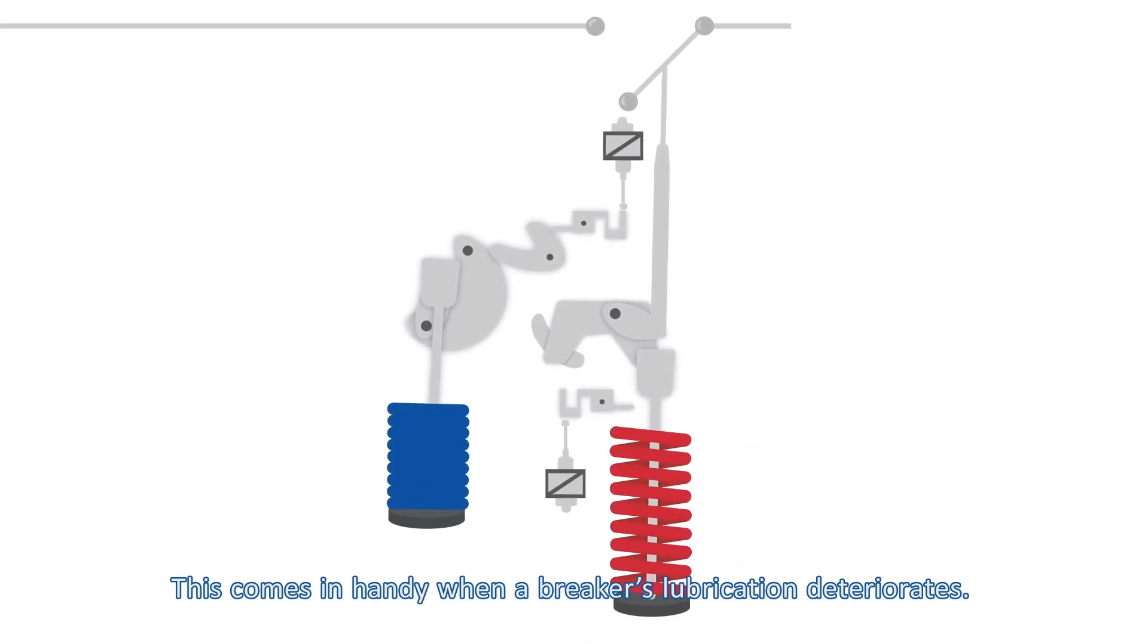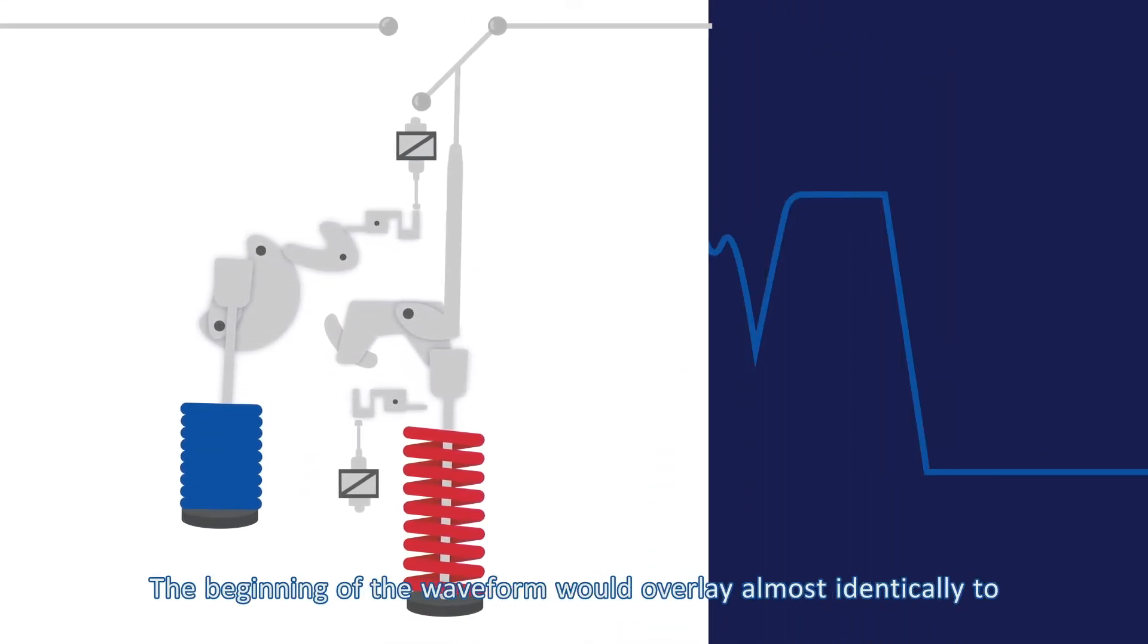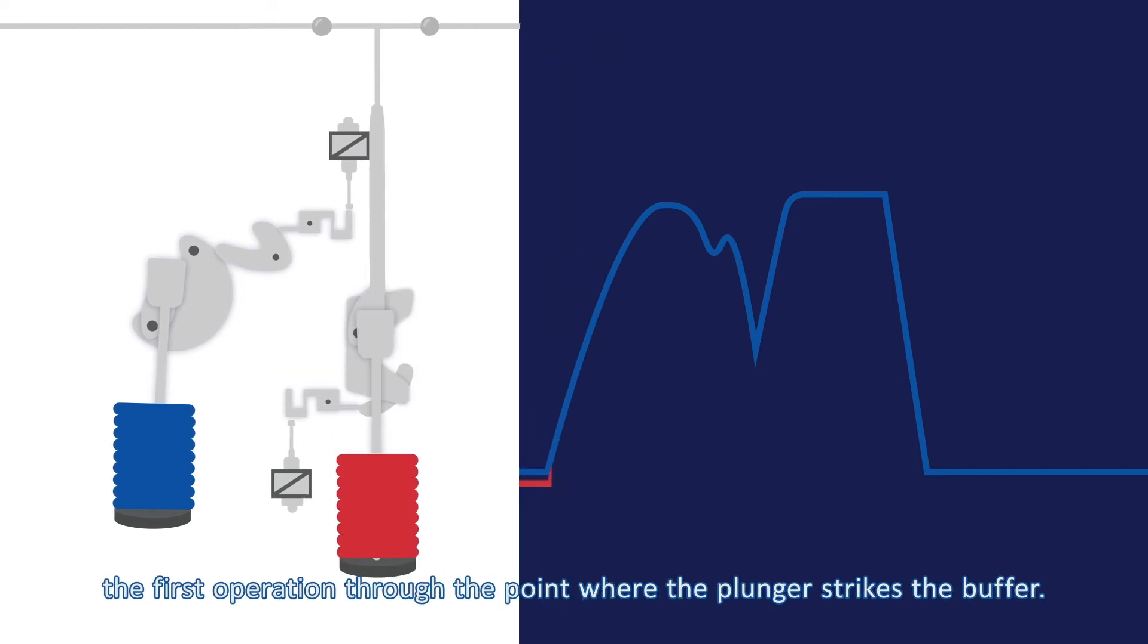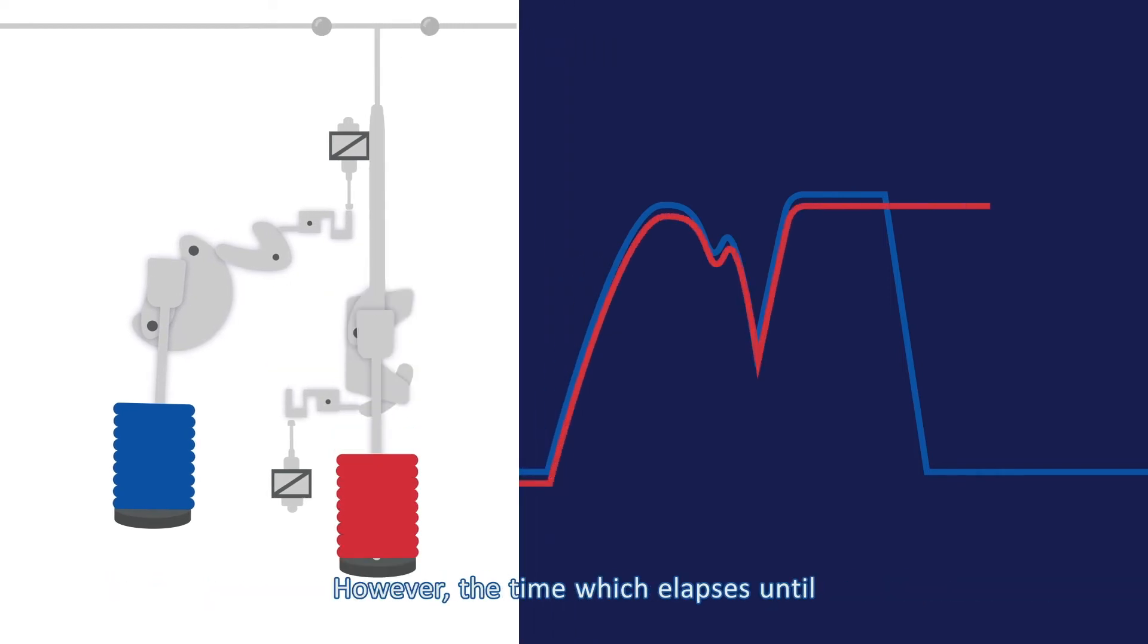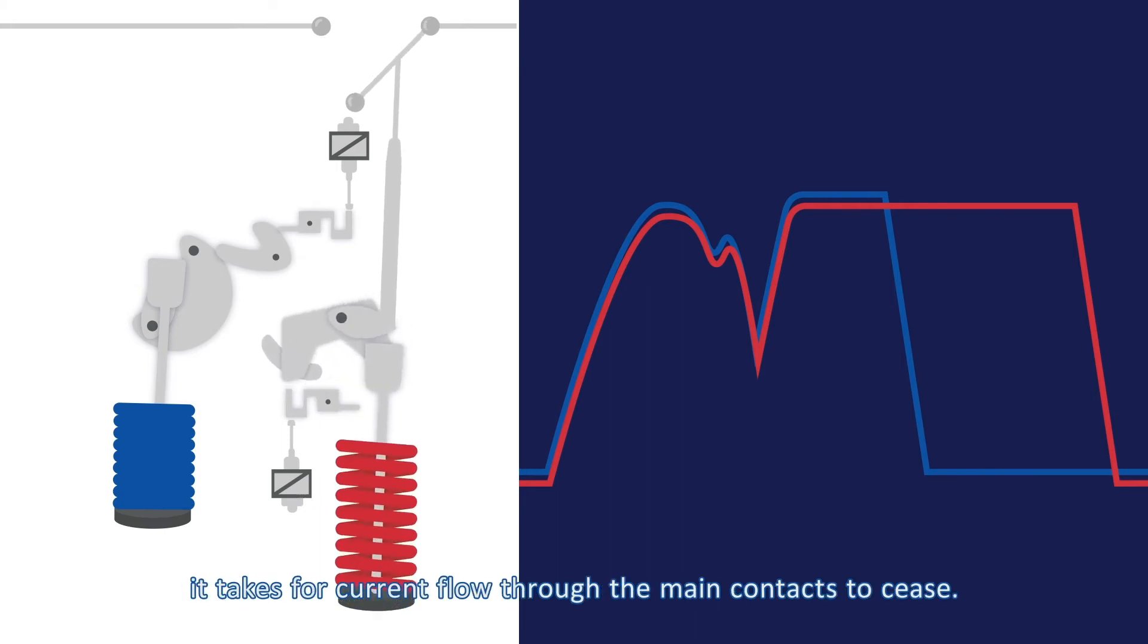This comes in handy when a breaker's lubrication deteriorates. The beginning of the waveform would overlay almost identically to the first operation through the point where the plunger strikes the buffer. However, the time which elapses until the falling edge of the coil current would increase. This increase would also be apparent in the amount of time it takes for current flow through the main contacts to cease.